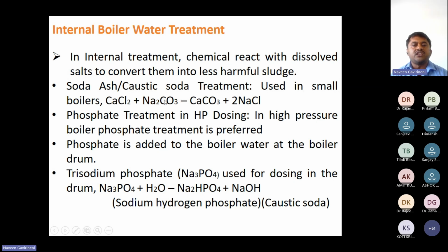These are for small boilers only. In big plants we do not use this because of the heavy deposition of salts. We use phosphate treatment, which is done with the HP dosing pump. This HP dosing pump supplies the dosing water to the boiler drum, as I already showed in the screenshot of the boiler drum. So this is supplied to the boiler drum to remove the impurities.